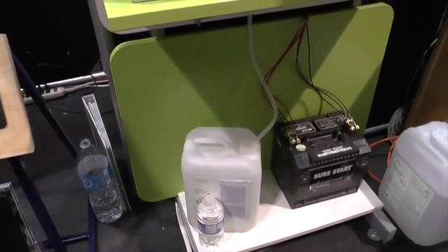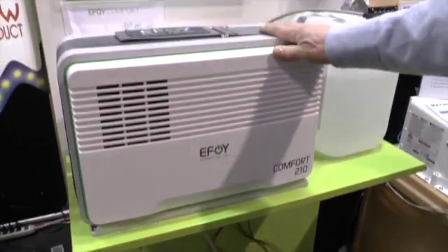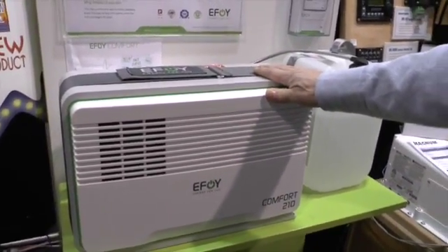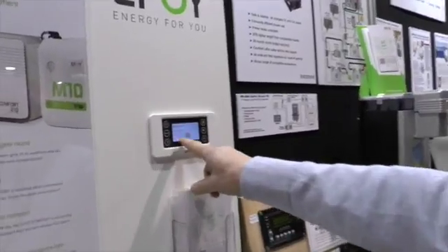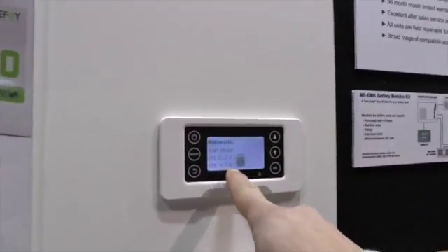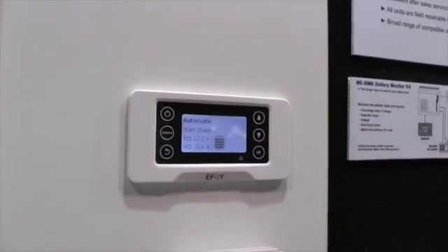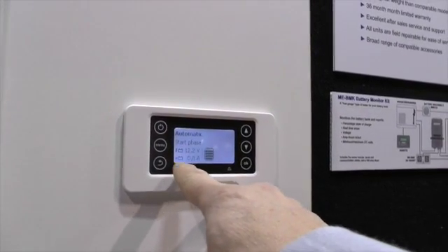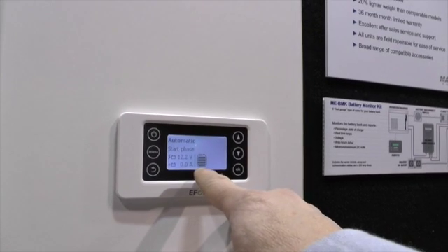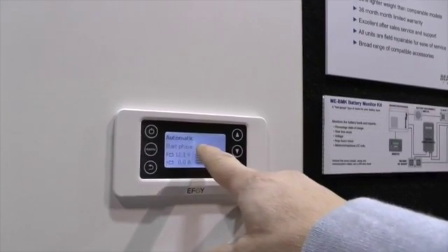The battery charger is a smart charger, so it'll take care of the batteries regardless of size or chemistry — it can all be set accordingly. In this particular case, it's going to come on when the batteries get down to 12.2 volts and continue to charge them until the battery gets up to 14.2. At the moment it's starting up — the battery voltage has dropped down to 12.2. We're running a little refrigerator here, and the unit is in start-up now. Very shortly it'll start putting some power back into the batteries and it'll shut off at 14.2.